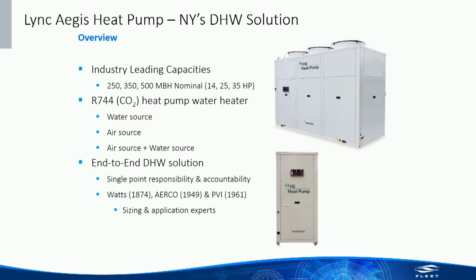That's 14, 25, and 35 horsepower. Again, those horsepowers are less of a concern for us here in New York because of the different classification of CO2. For reference, that 35 horsepower compressor only has about 80 pounds of refrigerant, so well under the 200-pound requirement.